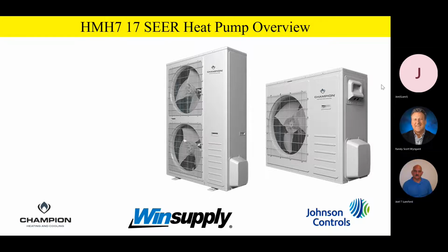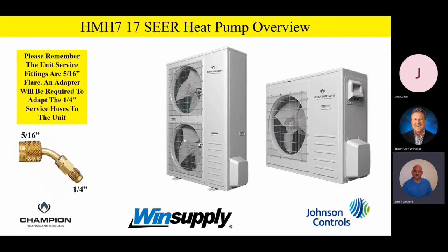So a couple things we'd like to talk about first and foremost as we start to get going here is we're going to please remember that the unit service fittings are actually 5/16. And so in order for the contractor to utilize their service gauges in a normal fashion, they're going to have to make sure and have this field adapter, or this flare adapter more specifically. And what it does is it takes that 5/16 fitting from the unit to the 1/4-inch fitting on their service hoses. Now, this is a very common adapter.